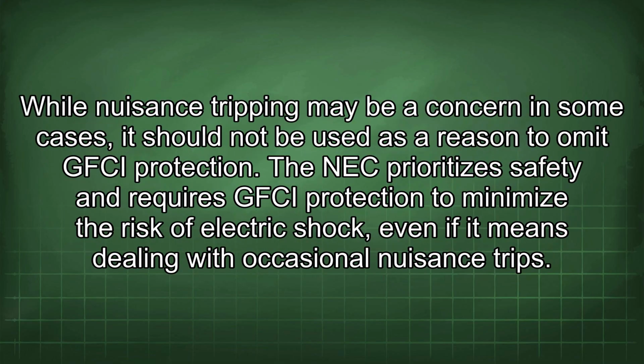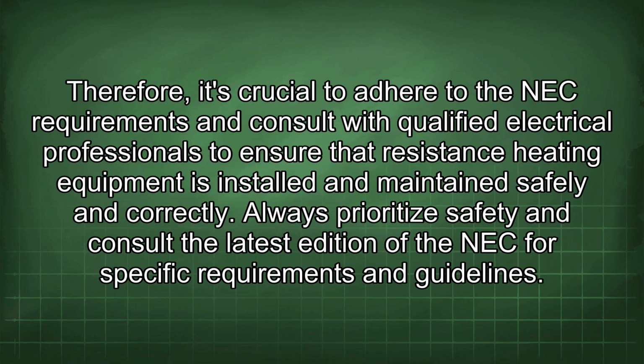While nuisance tripping may be a concern in some cases, it should not be used as a reason to omit GFCI protection. The NEC prioritizes safety and requires GFCI protection to minimize the risk of electric shock, even if it means dealing with occasional nuisance trips. Therefore, it's crucial to adhere to the NEC requirements and consult with qualified electrical professionals to ensure that resistance heating equipment is installed and maintained safely and correctly.